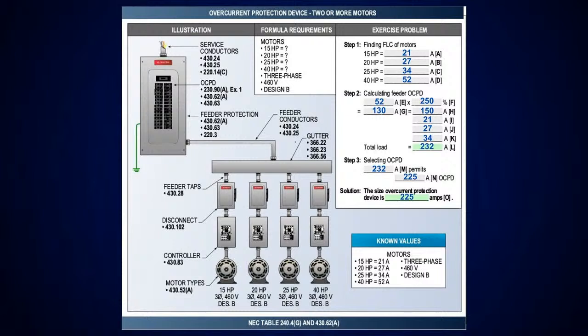So we changed this up from what they did, and that's probably like 3 cycles ago. I think they did this. Okay. But in this case, we got 4 motors. They're all three-phase 460-volt design B. I've got a 15, 20, 25, and 40 horsepower motor.